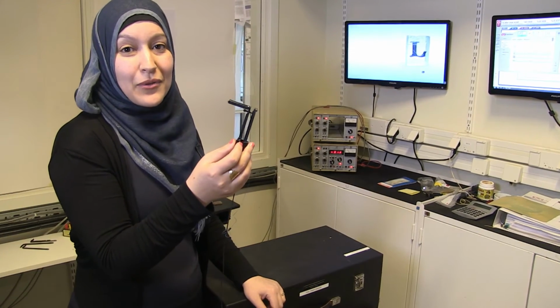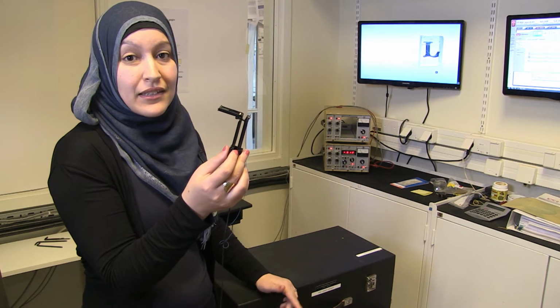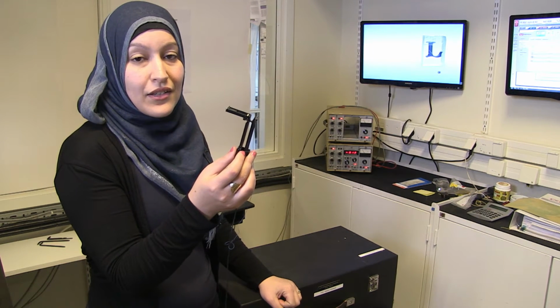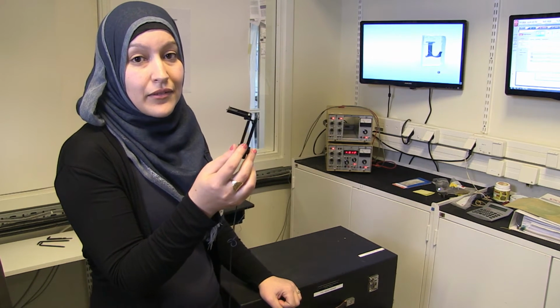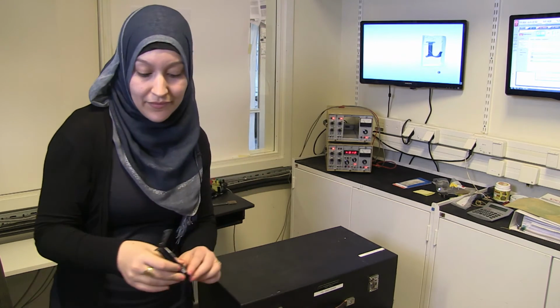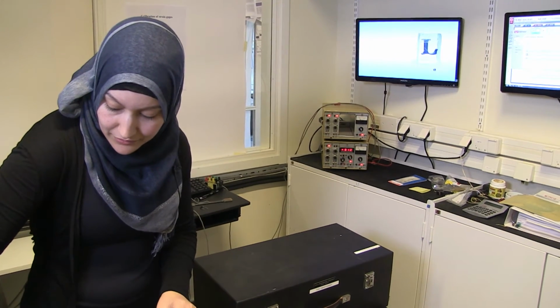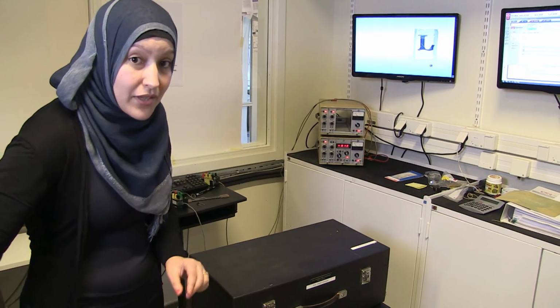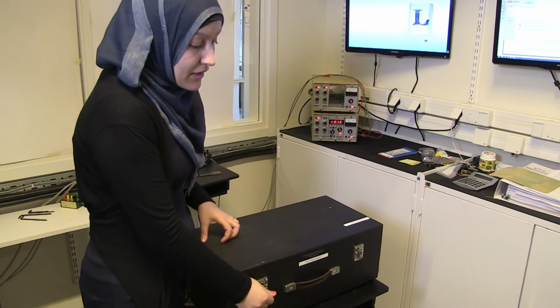Now I will show you how to calibrate physically the extensometer. As you know, the extensometer is a delicate and sensitive device. That's why we need to calibrate it regularly. For the calibration, I have here a special device.